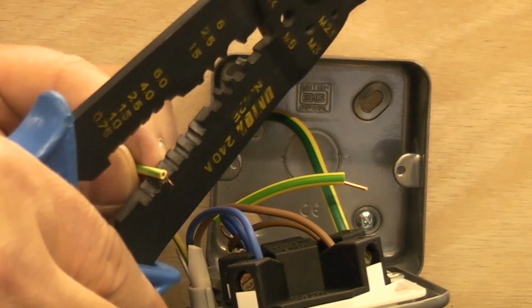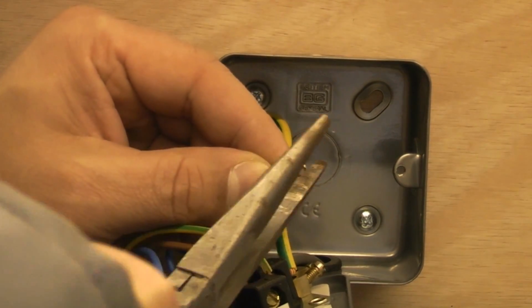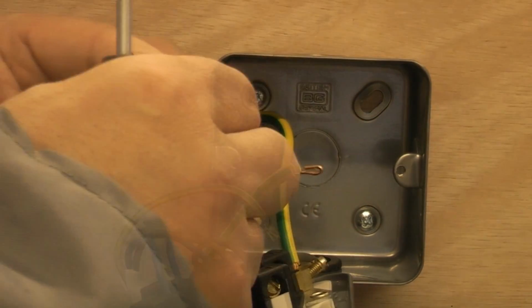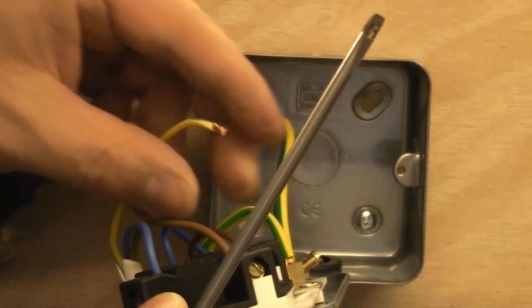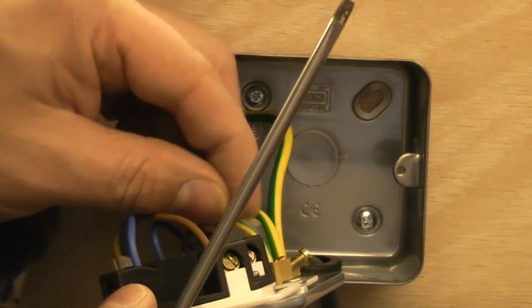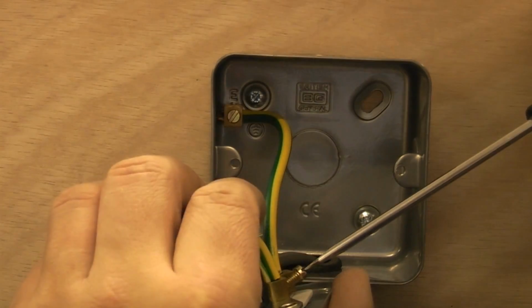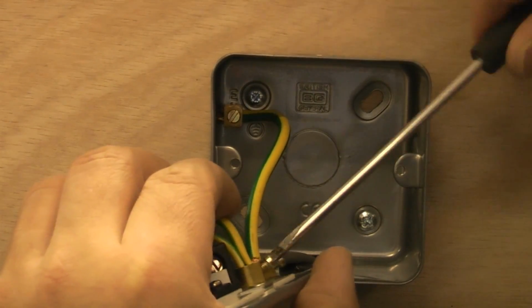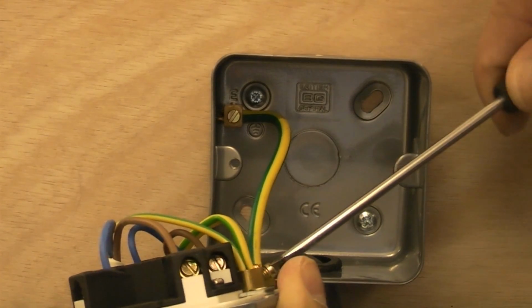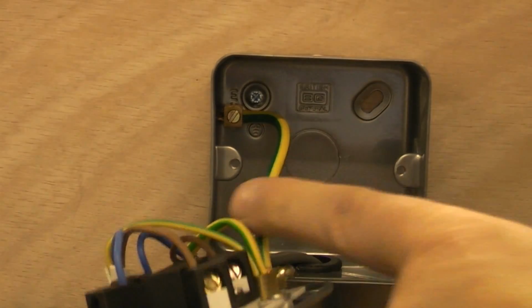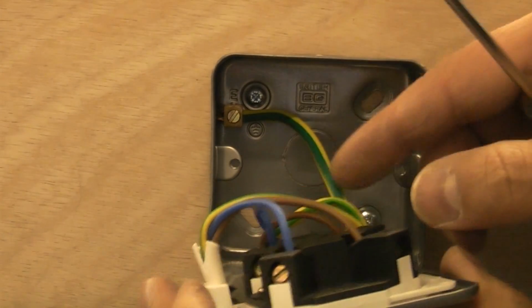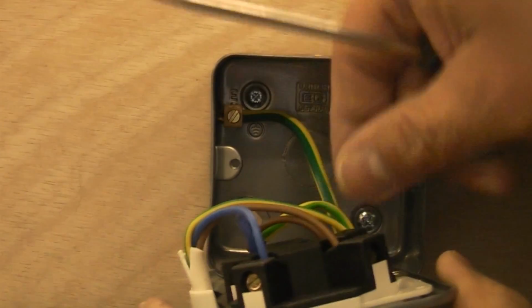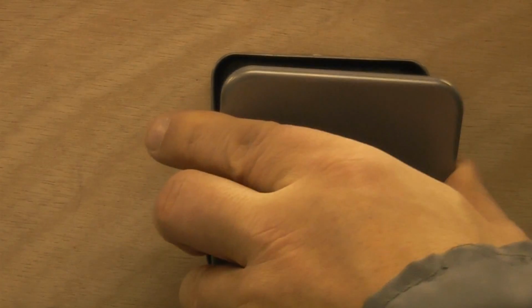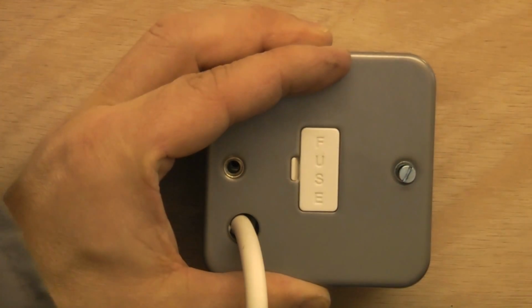Now we just need to strip off some insulation from the earth wire. We're now just going to bend back the conductor on the earth wire, and we'll bend that back on itself, and then we can terminate these earth wires into the remaining earthing terminal. The earth wire that I've used there is a little bit thick, but it's the only earthing wire that I actually had. So we now need to check that all those wires are secure, which they are. We can now put the face plate onto the back box. Can now replace the screws.